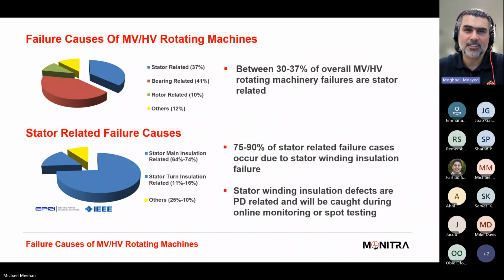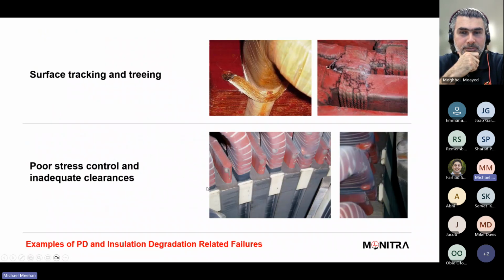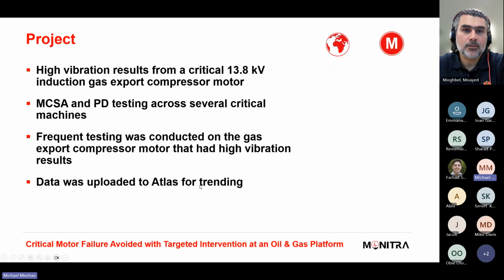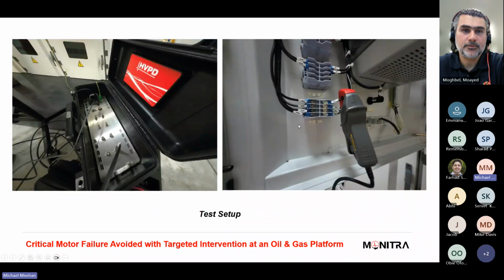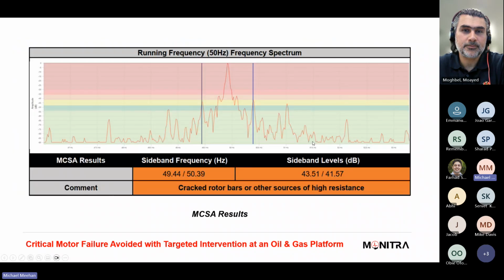Great, thank you. And what about the rotor? Rotor related is obviously not quite applicable in a generator, but on a typical squirrel cage motor you can do MCSA, which is very useful. At the end of this presentation I have an MCSA case study. It's really straightforward to do: going onto the CTs of the motor, clipping on using a clamp meter, and then you can look at the sidebands. If the sidebands are prominent, that can lead to a cracked rotor bar diagnosis.